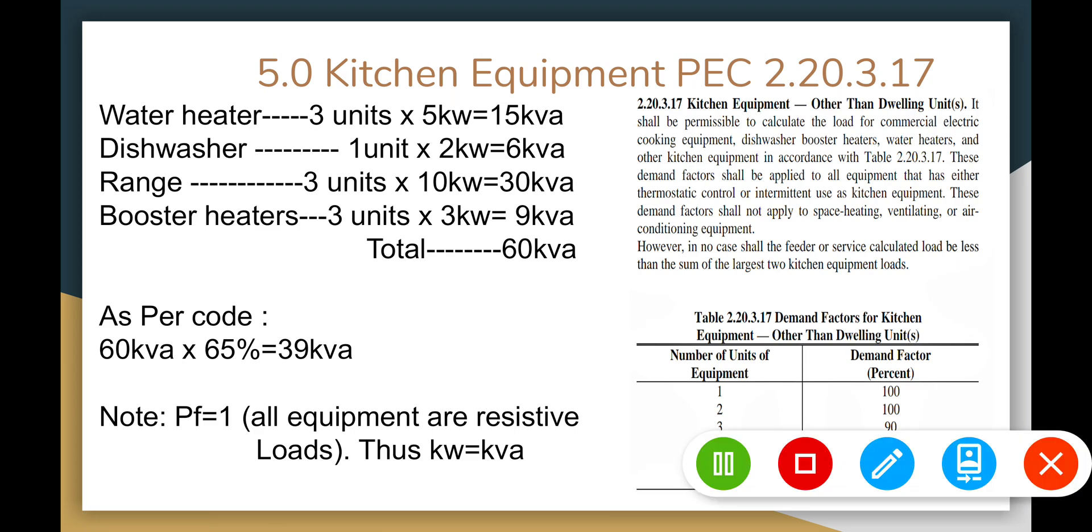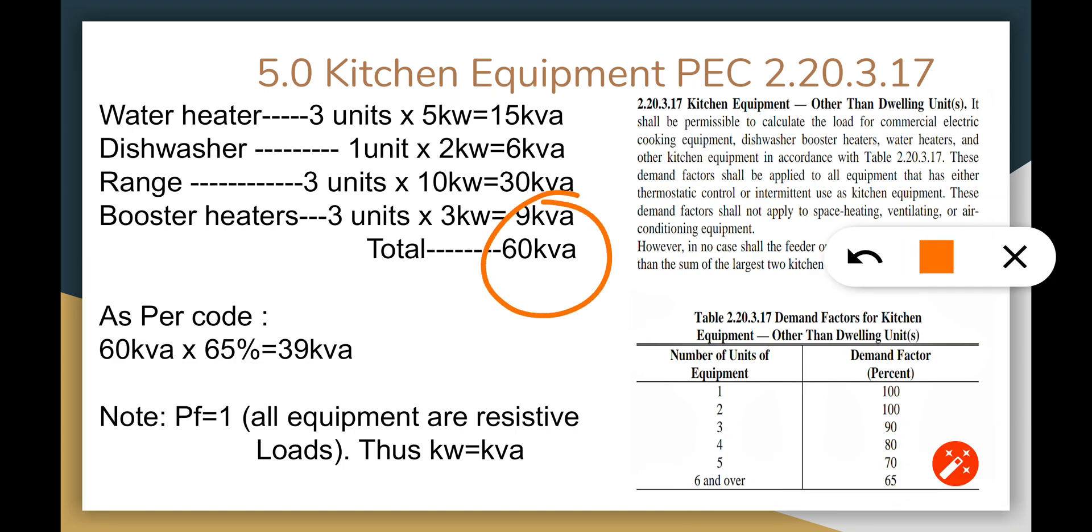For the kitchen equipment, we have a total of 60 kVA. The power factor is one because these are heaters, all resistive loads, so one kilowatt is equal to one kVA. We have more than six units of appliances, so we use 65 percent based on the code, so we get 39 kVA.